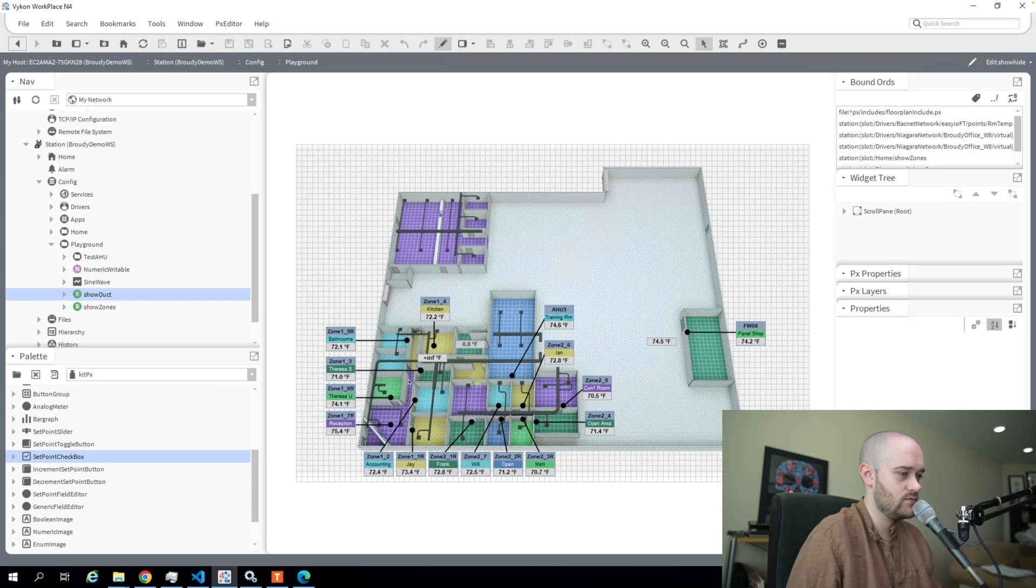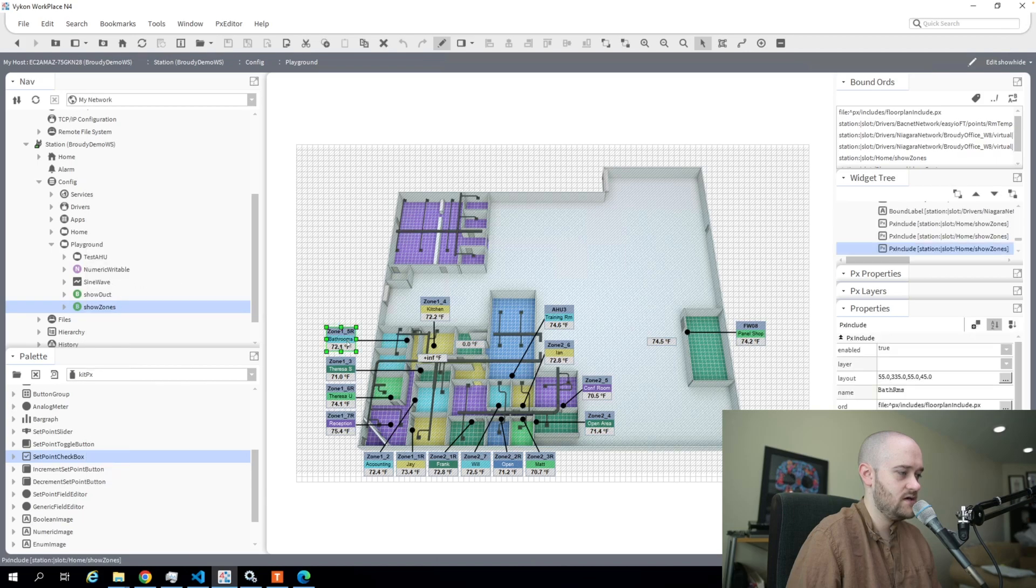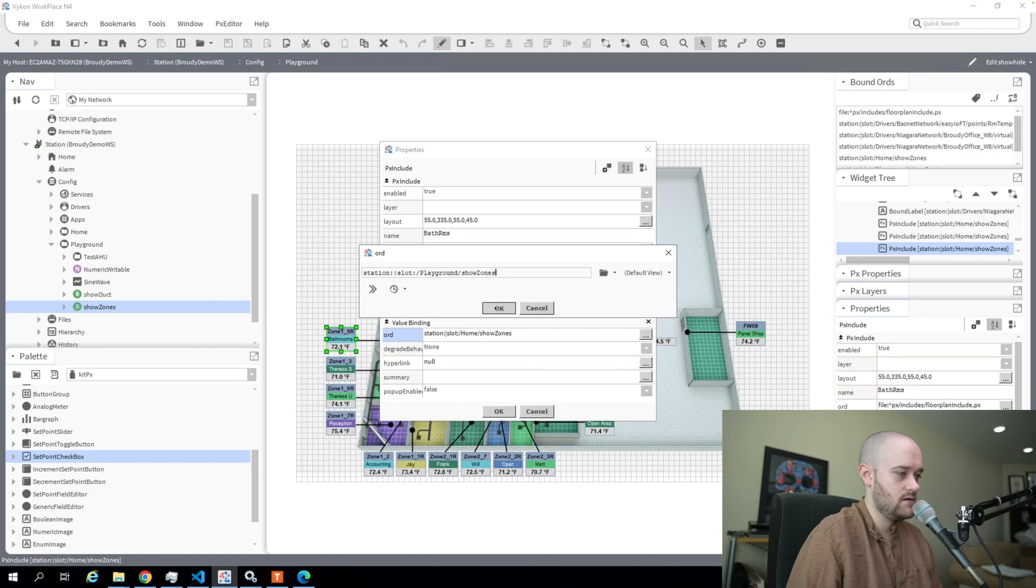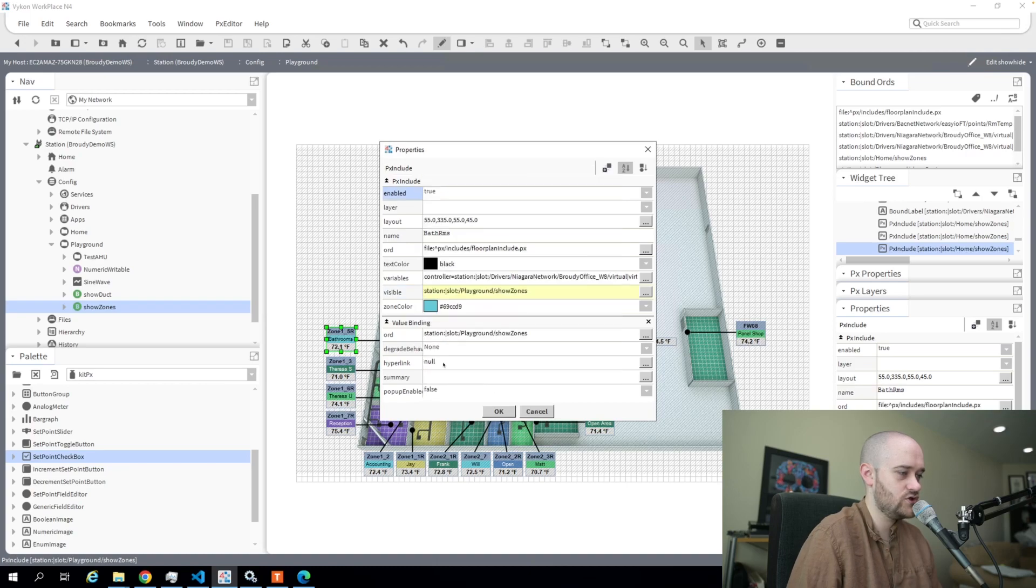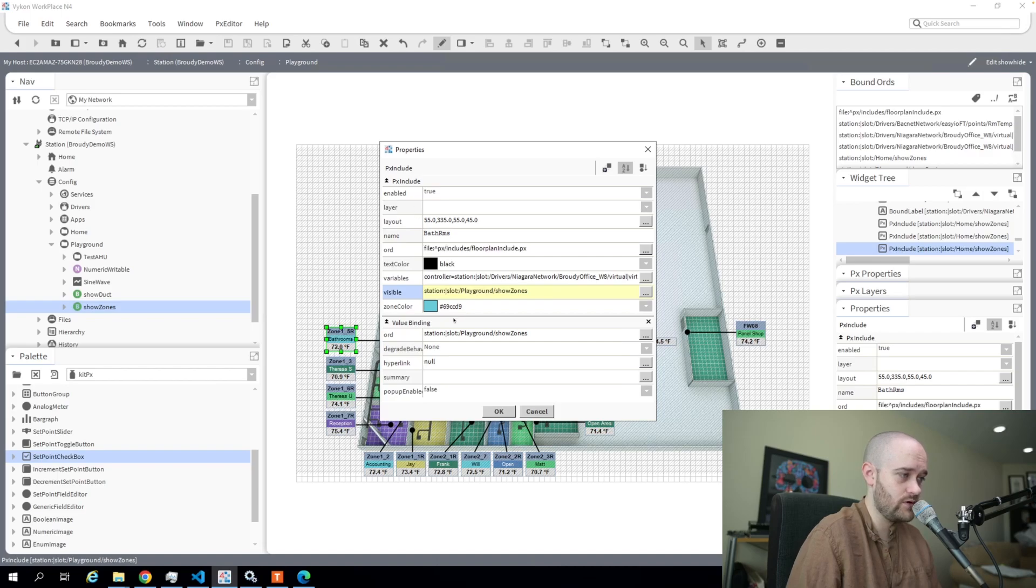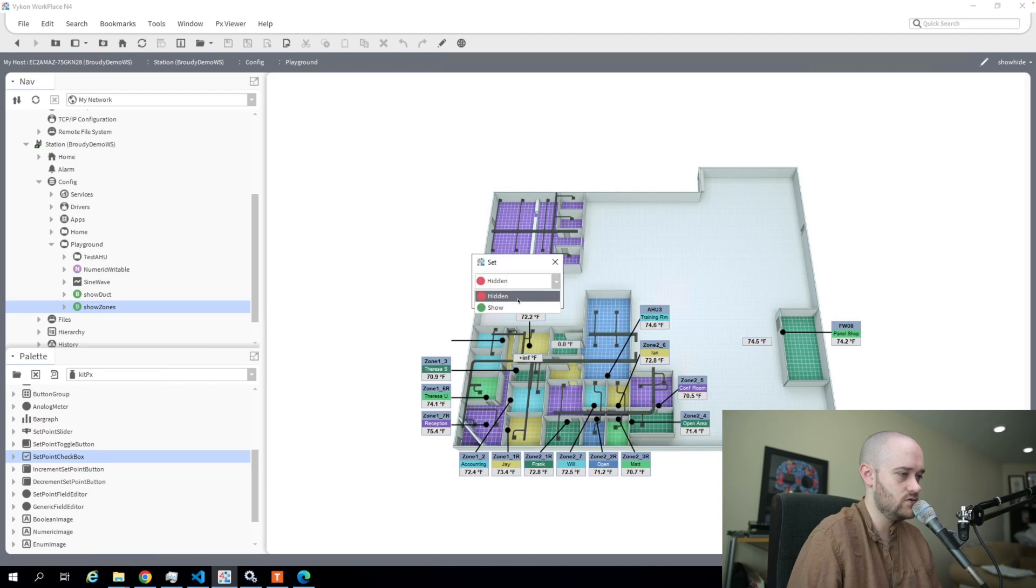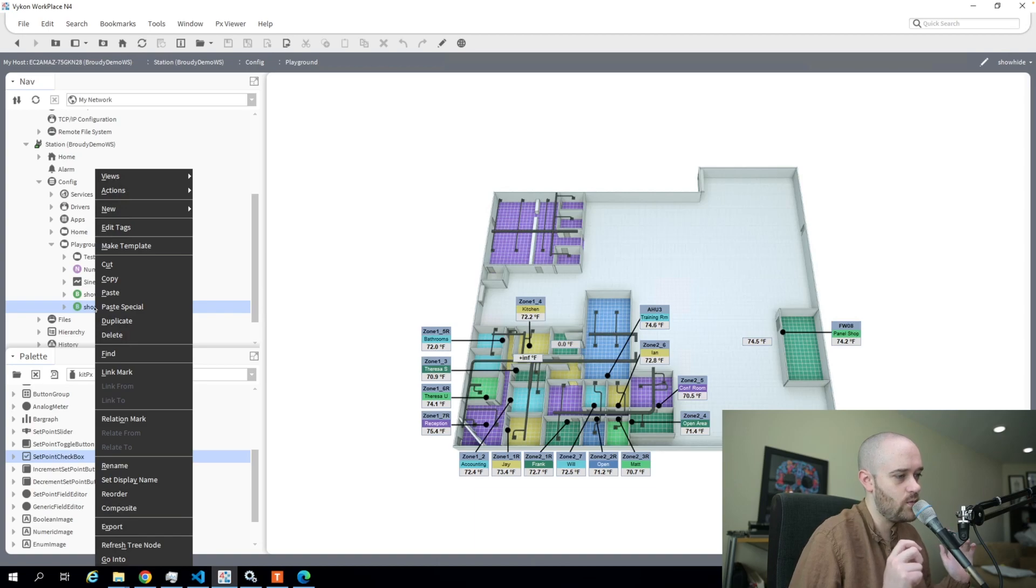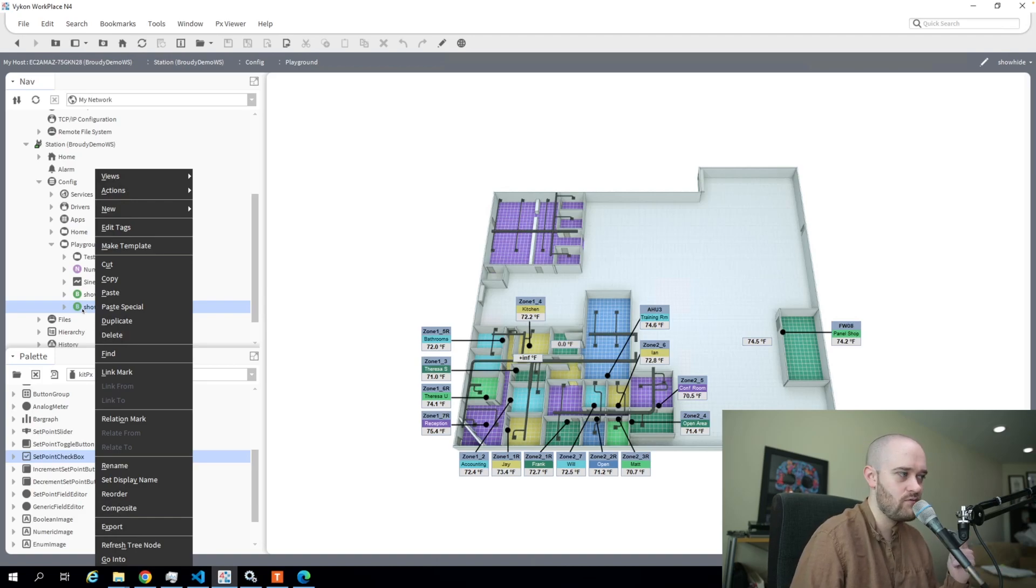And the next thing that we'll do is we'll do this for all of the zones. Same thing, except I already had this in there, so on false I want this not to show, and on true I want it to show. The way I did this was I just right-clicked on the visible property and animated it. You can do this for any of these properties pretty much. You can animate them based on a binding that you add into the point. You can have multiple bindings too. Now I'm going to fast forward a bit and I'll come back when all of my floor plan items for the zones are set with that visibility animation for this point.